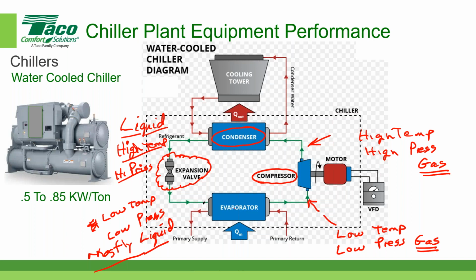And then when it gets into the evaporator, that's when it absorbs heat from the return water temperature. And this is a chilled water system. So this primary supply and primary return, that's your chilled water that's in your system. That's called the chilled water. And so it's going to enter the evaporator as a liquid.